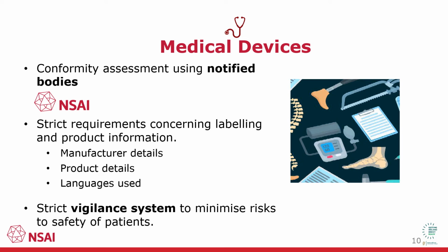An extensive vigilance system was set up under the medical device directives to minimise risks to the safety of patients, users and others. An adverse incident is an event during use of the device which might lead to or might have led to death of a patient or user or of other persons or to a serious deterioration in their state of health. Adverse event reporting requirements must be followed as outlined in the MDD or MDR as applicable, and associated guidance documents.